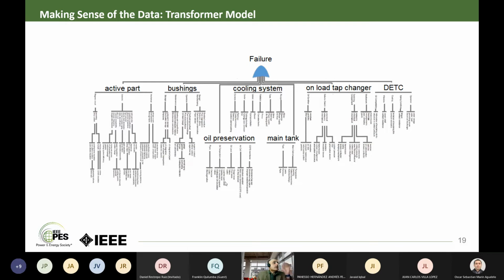The idea is looking at that data and understanding all of the different failure modes. How do you create the picture of the health of the transformer? That is really the problem we are trying to solve in this case. We are doing this for one transformer, but if you can do it for one transformer, the same logic can be replicated for all the other transformers. We can do this for 1,000 transformers, for 10,000 transformers, as long as you have the correct data coming in, and as long as you have the algorithm that is ingesting all of this data and making sense of it.